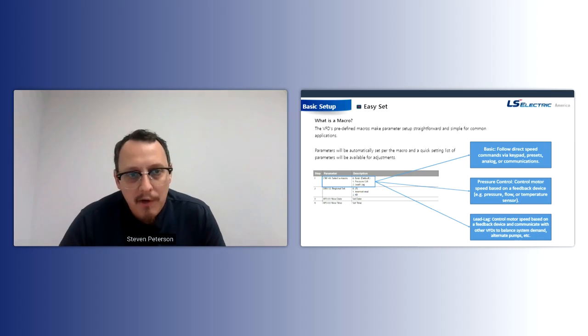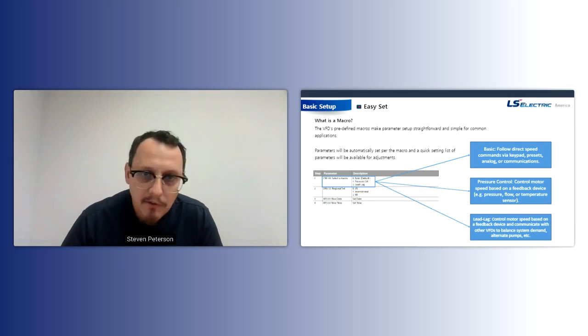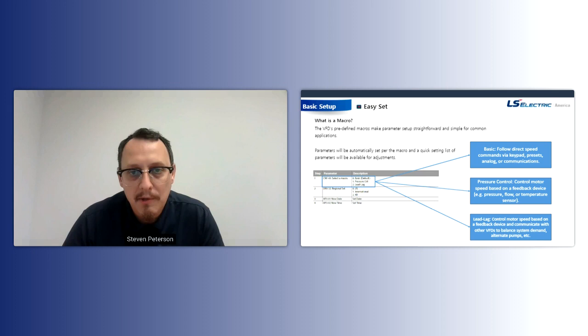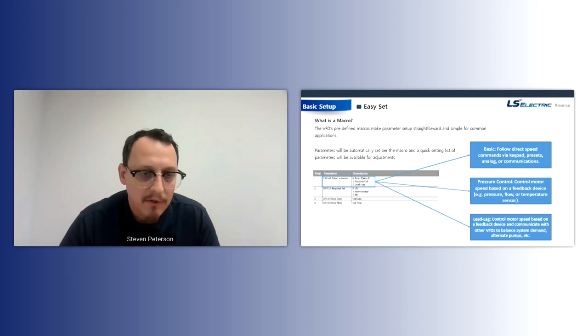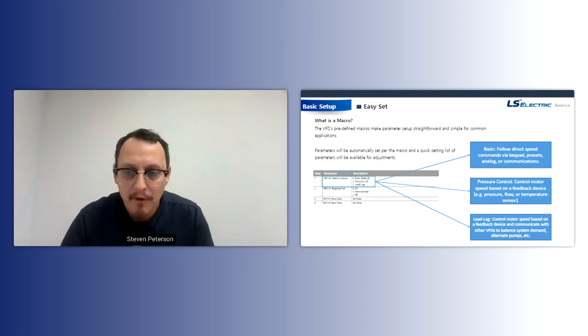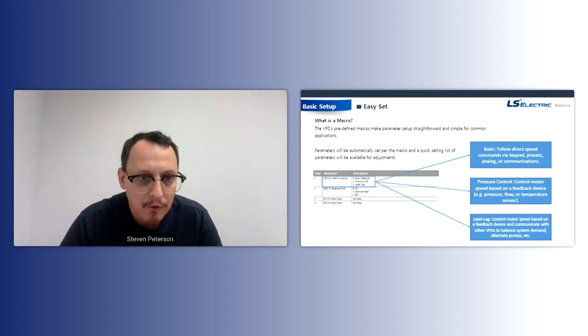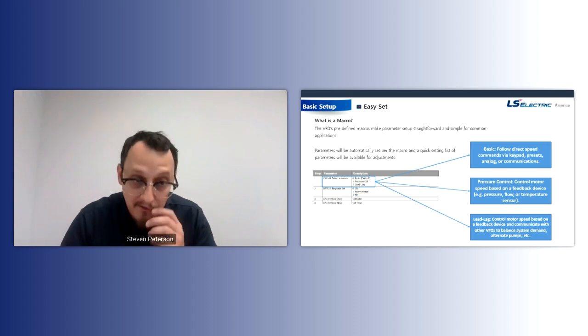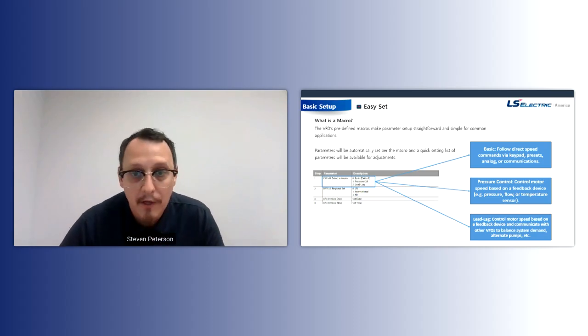So before we do that, I want to tell you that a macro is pretty much a predefined set of parameters that is meant to make life easier for whoever's commissioning the VFD and doing the startup, okay? So there's going to be some common parameters that are set up, and then it's also going to list all of those parameters in a macro list. So they're easy to adjust where you don't need to jump through 10 or 15 different groups. You just go down that list and you answer the questions, and then the drive is set up.